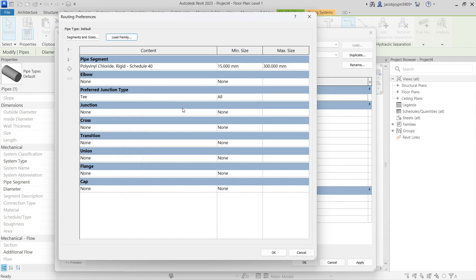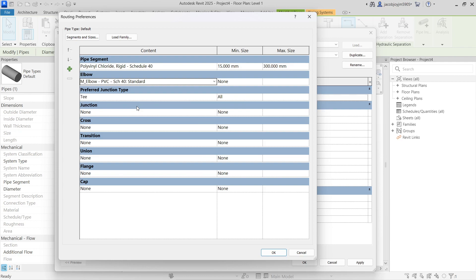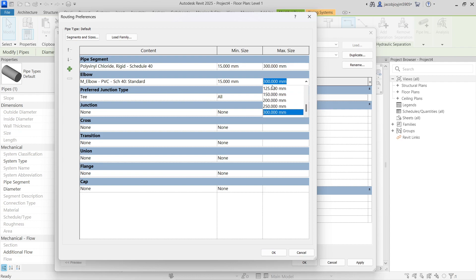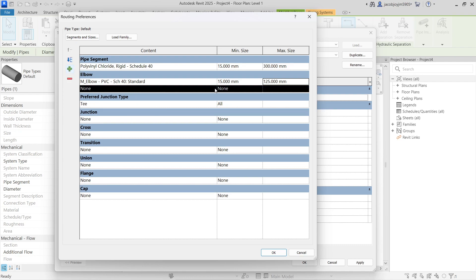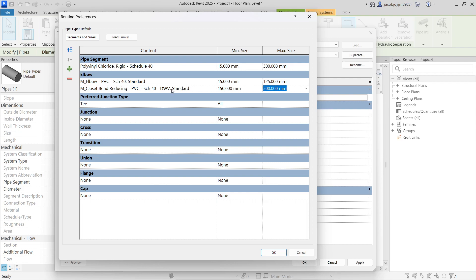Once loaded, you can select the Elbow type as PVC Standard and set the size to All. If you want, for sizes 15 to 125 use one type, and for larger sizes — say 150 to 300 — choose a different type. For the preferred junction type, it's better to keep it as T.